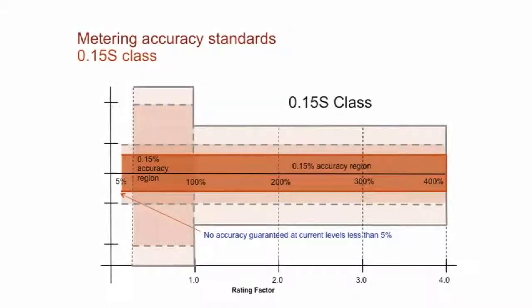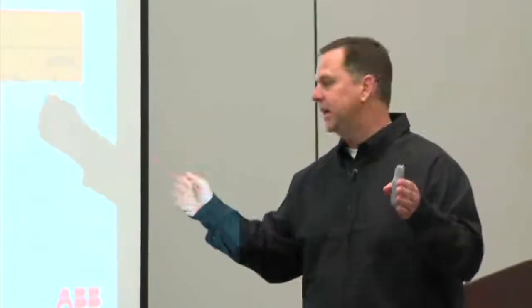The 0.15 S class is the most highly accurate recognized class within the IEEE. And that basically goes from 5% of your nominal current through the rating factor, all at 0.15%. So we've significantly narrowed down the band of inaccuracy that gets eliminated, and we've extended the range a little bit as well. Now, ABB also makes instrument transformers at the medium voltage level, which can go beyond the 0.15 S class. Not any more accurate, but we've increased the range for that, all the way down to 1% of your nominal current. So again, if we go back to that example of a 200:5 rated CT, it would measure any amps from 200 through a rating factor of 1.5 in this case to 300 amps, all at 0.15% accuracy. So you have a very, very highly accurate current transformer all along the whole current or the whole load feeding into your meter in order to get more accurate readings.